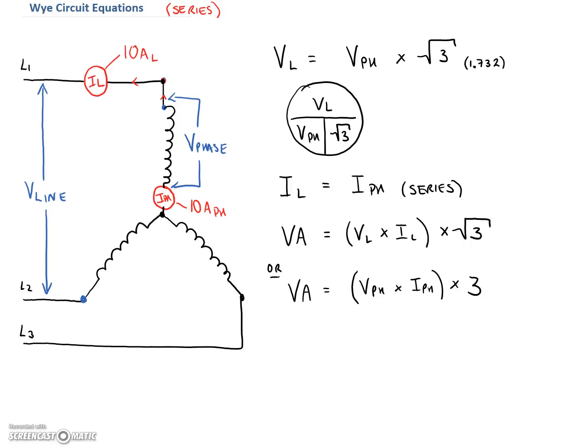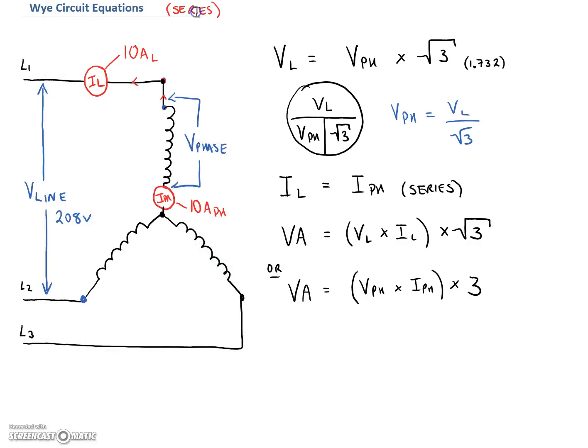Let's take an arbitrary voltage — 208 volts for our line voltage. If we want to find our phase voltage, our phase voltage is equal to V_line divided by root 3. So we take 208 volts and divide by the square root of 3. And you can see that the voltage on the phase is going to be 120 volts. So 208 and 120 are always going to go together. Our phase voltage here is going to be 120 volts on the phase.